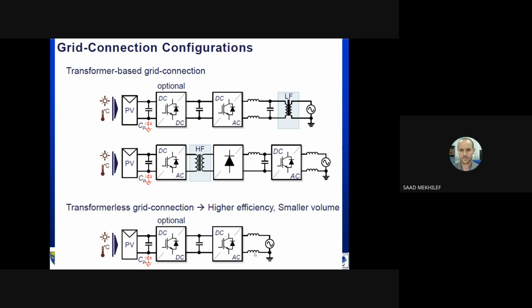Sometimes on the grid you have transients, not a fault, so how can you differentiate between a transient and a fault? Your control system should be able to determine whether it is a fault, because if it is a fault, you need to disconnect your PV system from the grid immediately, so the fault cannot be transferred. Then you have to reconnect later, when the fault goes away. So you have a lot of connection and disconnection. Here, in the transformerless, the control plays a very big role in having a safe grid-connected system. But I think it's not an issue anymore, because now we have very fast, very advanced controllers which can respond fast to this kind of events.